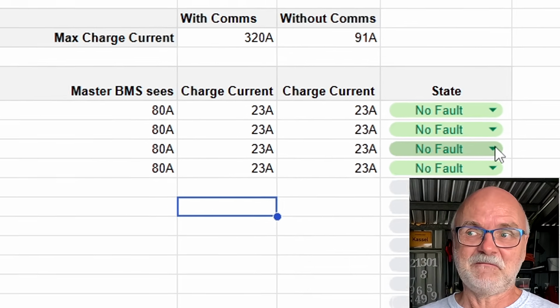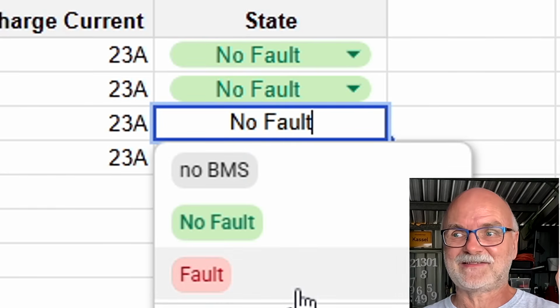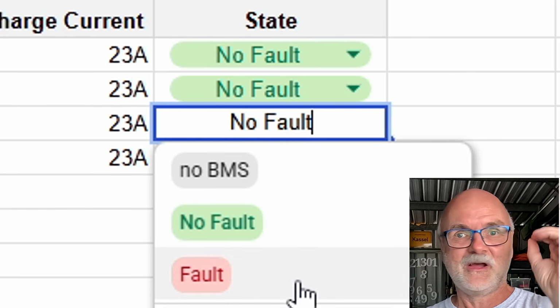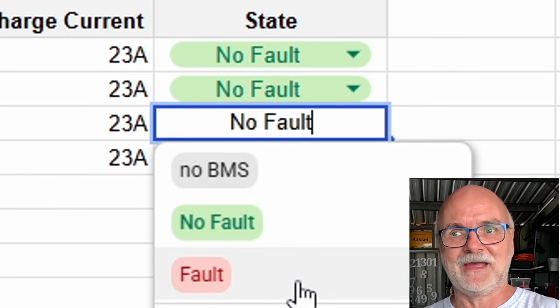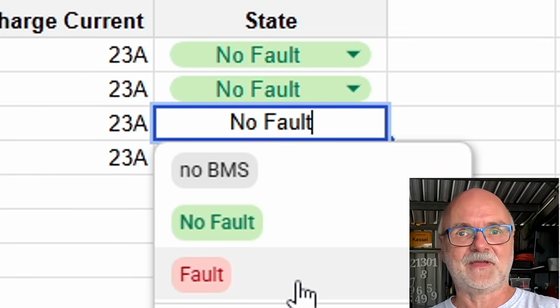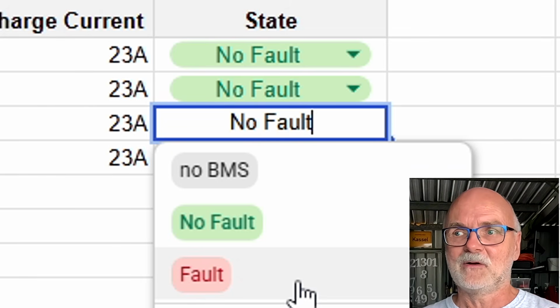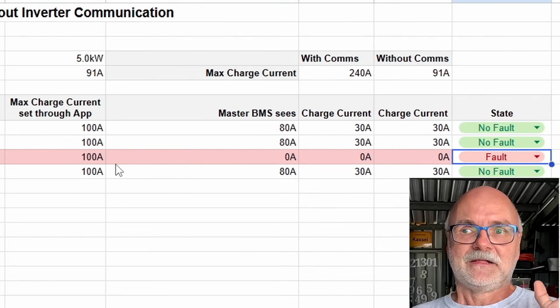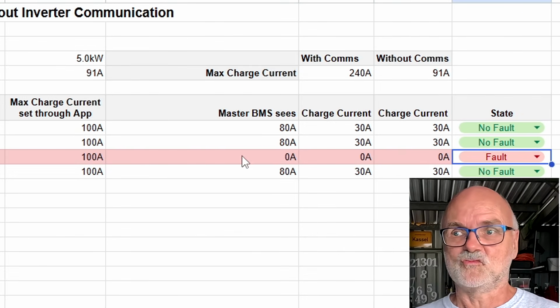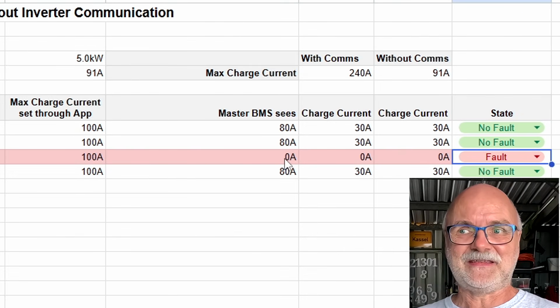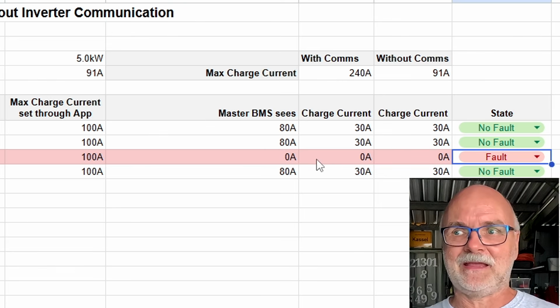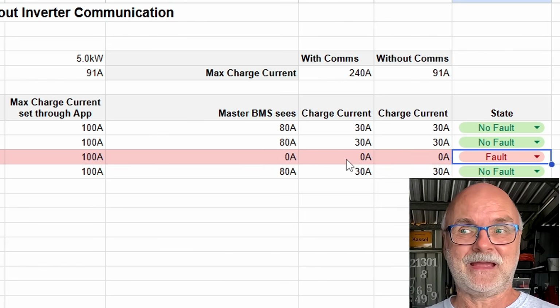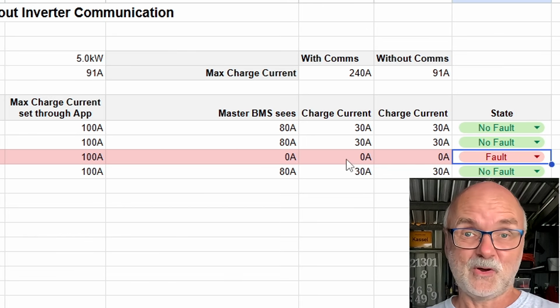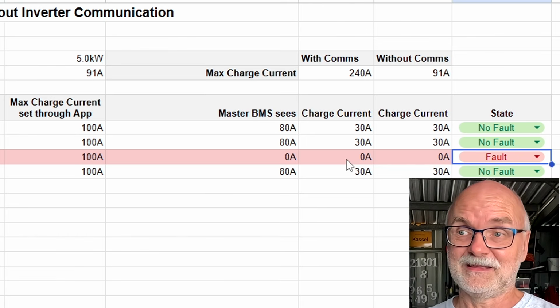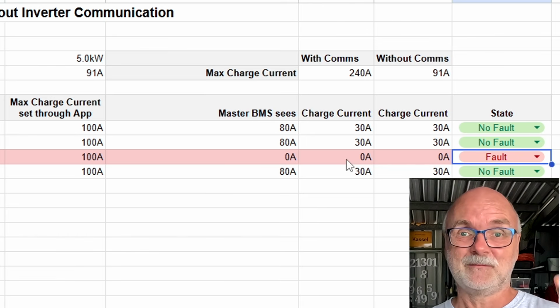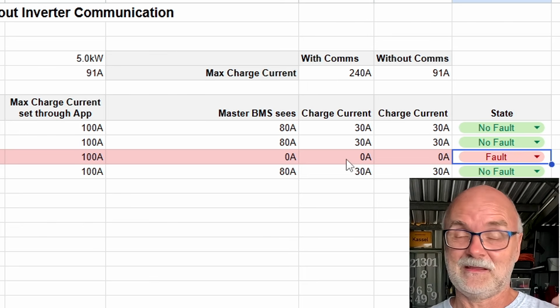So let's see, one of the BMSs now has a fault. Yeah, exactly what we have tested before. Over voltage protection. You've got a runner at 55 volts. One of your cells has hit 3.65 volts. We've got a fault. Bam. Your BMS goes out. Red line. The master sees 0 amps coming from this BMS. The charge current into this BMS is 0 amps because the MOSFETs have turned off, right? There's a physical disconnection between your charger and the BMS, if the BMS works.